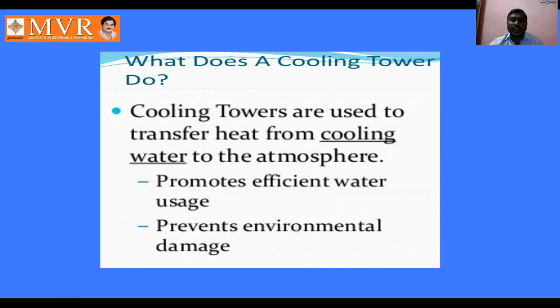We are not using any fans in the natural draft cooling tower. Without using any fan, we get the air from the atmosphere, because there is a pressure difference between the cooling tower and the atmosphere. Due to this pressure difference, the air directly enters the cooling tower.